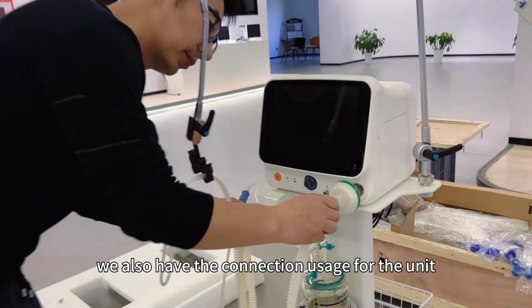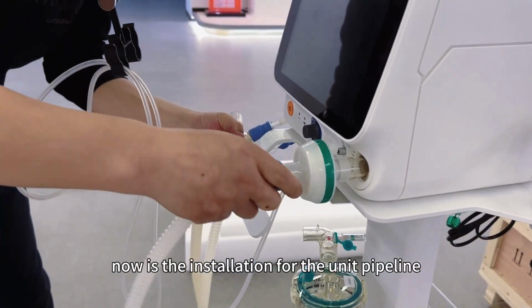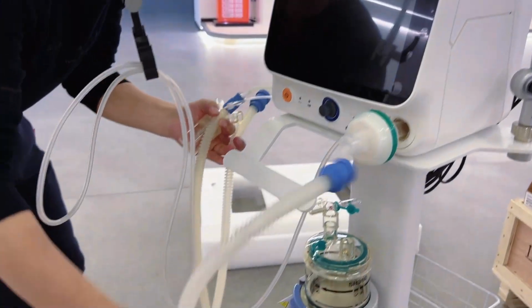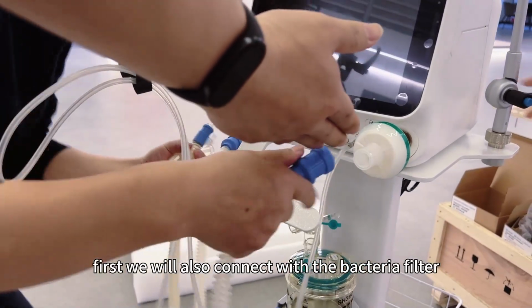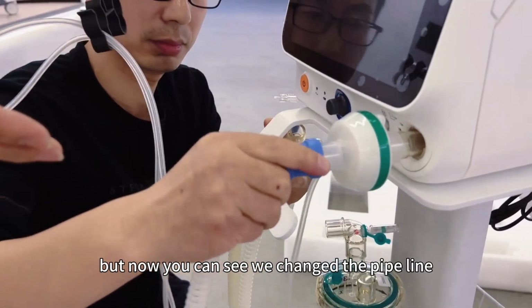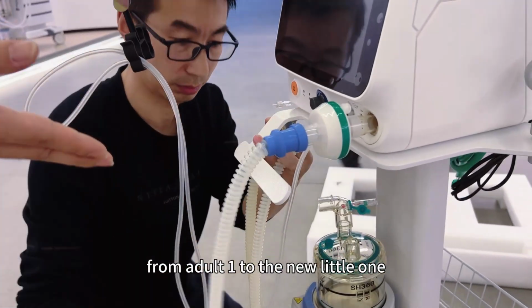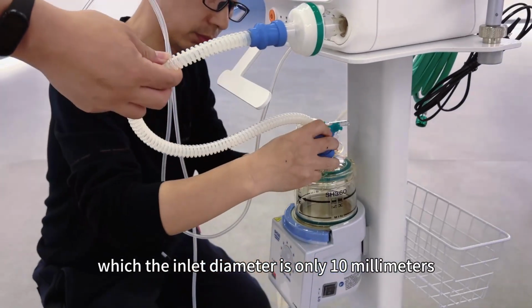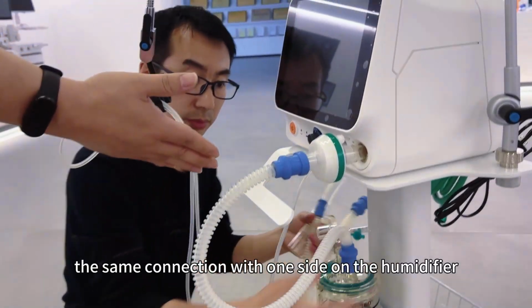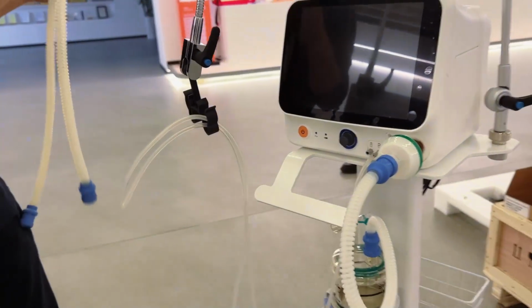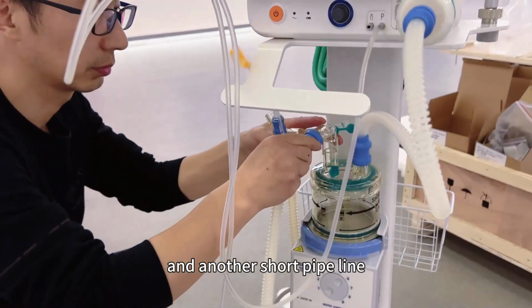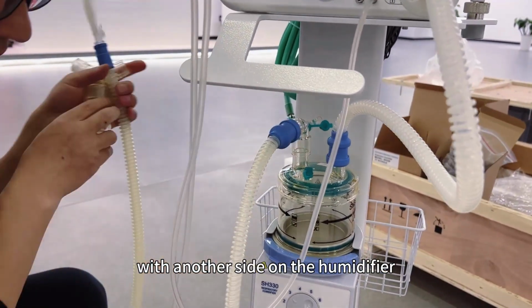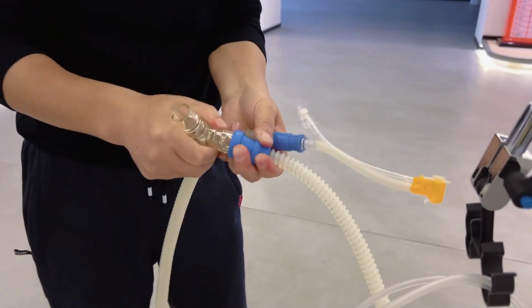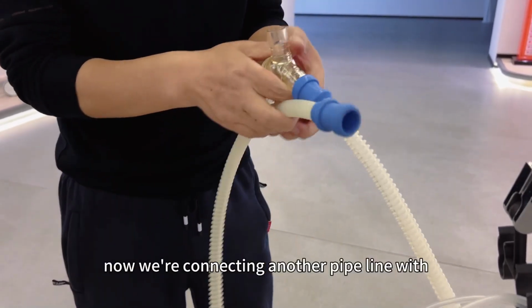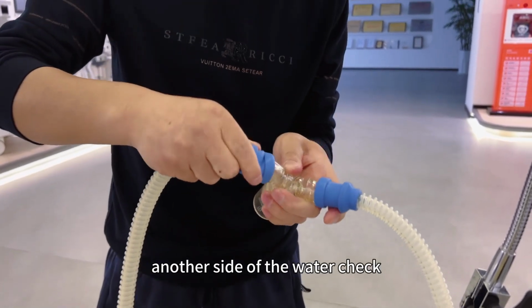Okay, so for this model, we also have the connection usage for the neonatal. Now is the installation for the neonatal pipeline. First, we will also connect with the bacterial filter. But now you can see we changed the pipeline from the adult one to the neonatal one, which has an inner diameter of only 10 millimeters. The same connection with one side on the humidifier. And another short pipeline with another side on the humidifier. And then we will connect it with the water trap.